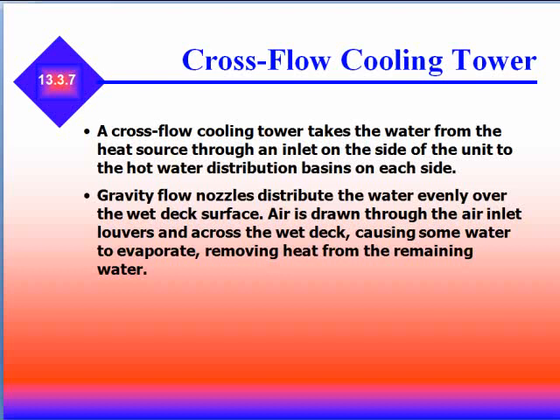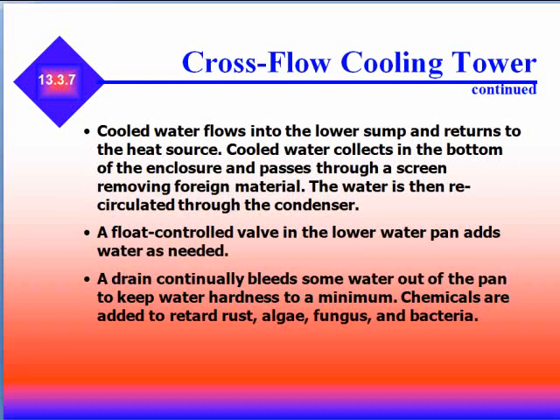Gravity flow nozzles distribute the water evenly over the deck surface. Air is drawn through inlet louvers and across the wet deck, causing some water to evaporate and removing heat from the remaining water. Cooled water flows into the lower sump and returns to the heat source, collecting in the bottom of the enclosure, passing through a screen to remove foreign material, and then the water is recirculated through the condenser.